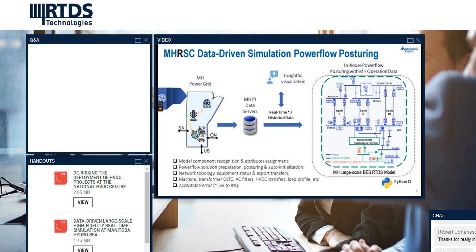Realizing this complexity and the need to seamlessly posture the power flow of our large-scale simulation model, we internally developed a high-fidelity tool in Python that would automate the power flow scenario adjustment using either near real-time or historical system operating data acquired from a Manitoba Hydro Central Operation Repository PI data servers within minutes. This tool recognizes the model components and changes the attributes accordingly, adjusting network topologies, equipment status, export transfer levels, machine settings, transformer OLTC positions, AC filter, HVDC AC filter status, HVDC transfer and power loads, as well as load profiles, etc.